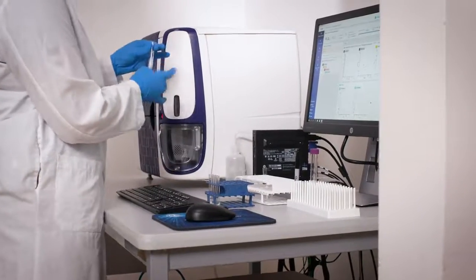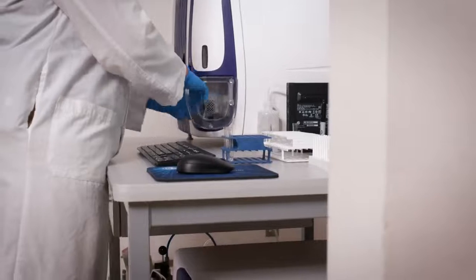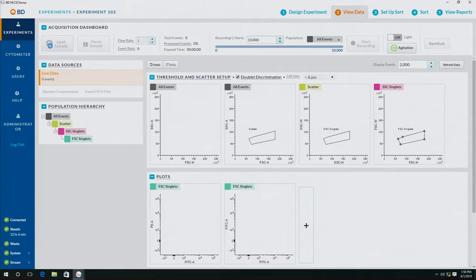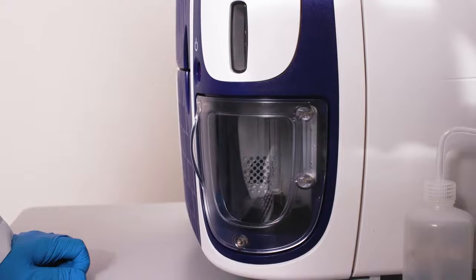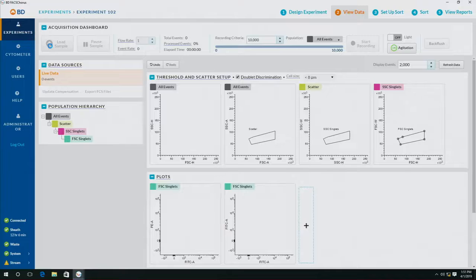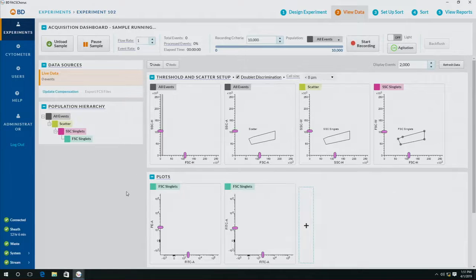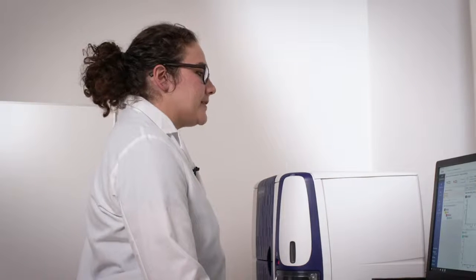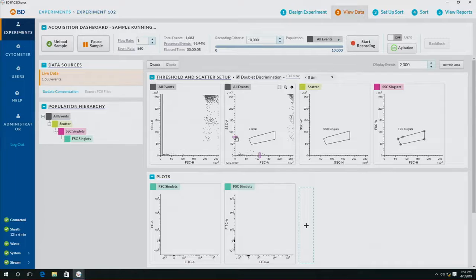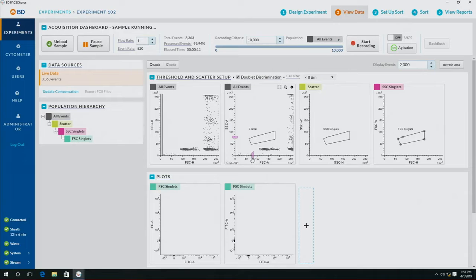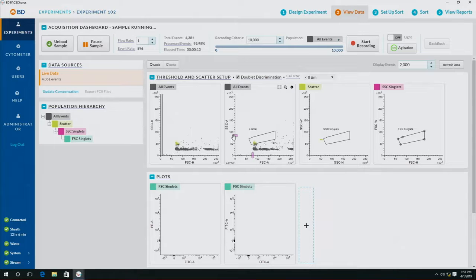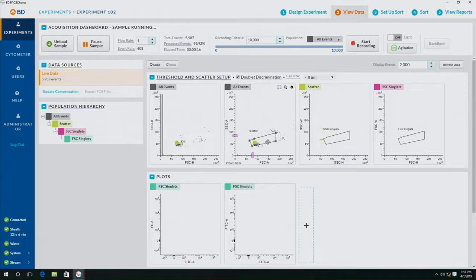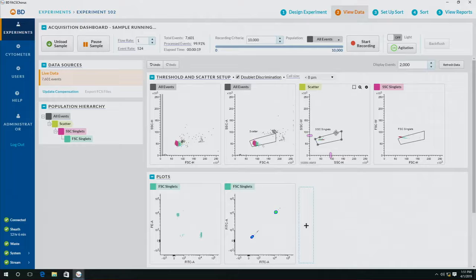Now to bring my sample on scale, I'm going to use those pink sliders to adjust the different settings until I see my bead population, and I can click refresh data. Now that I see my beads, I'm going to adjust my gate and remove all the doublets to be sure I have the right population on my plots.